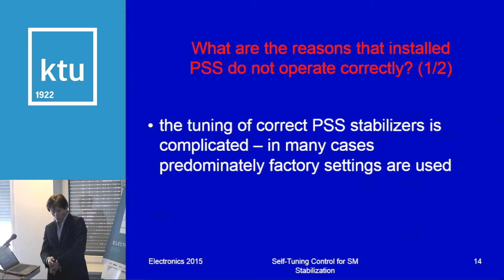So what are the reasons the installed stabilizers don't operate correctly? First, when we buy an excitation system with a stabilizer, we have to tune the parameters, which is very difficult and time consuming. Therefore some operators use factory settings, and these factory settings enable damping for some synchronous generators, but not for all, and not in all operating points.